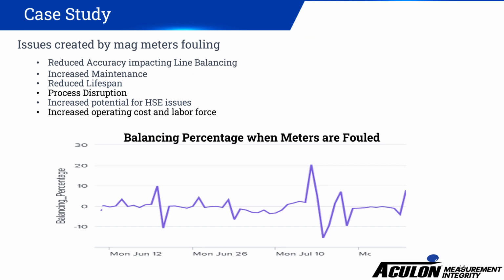Issues created by mag meter fouling: a reduction in accuracy impacting line balancing and leak detection, as usually oil and organic buildups cause meters to read low; an increase in maintenance, both cost and time; a reduced lifespan of the meters, as meters are often pulled out, cleaned, and then placed back into service. This also causes a reduction in meter life, as often most of the meters will be pulled out, and then while being placed back in, there will be damage to both the internal liner and the exposed liner on the end.